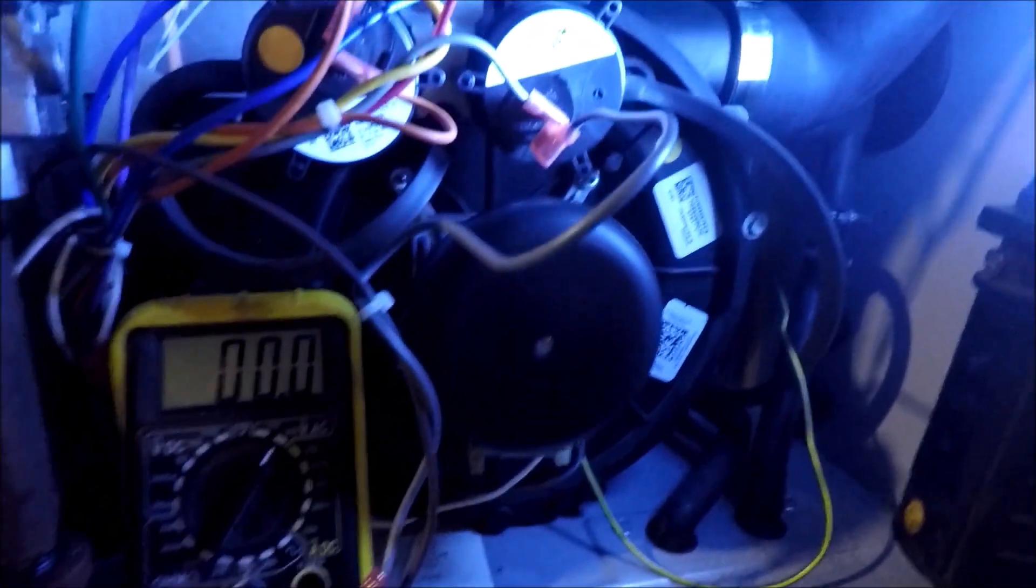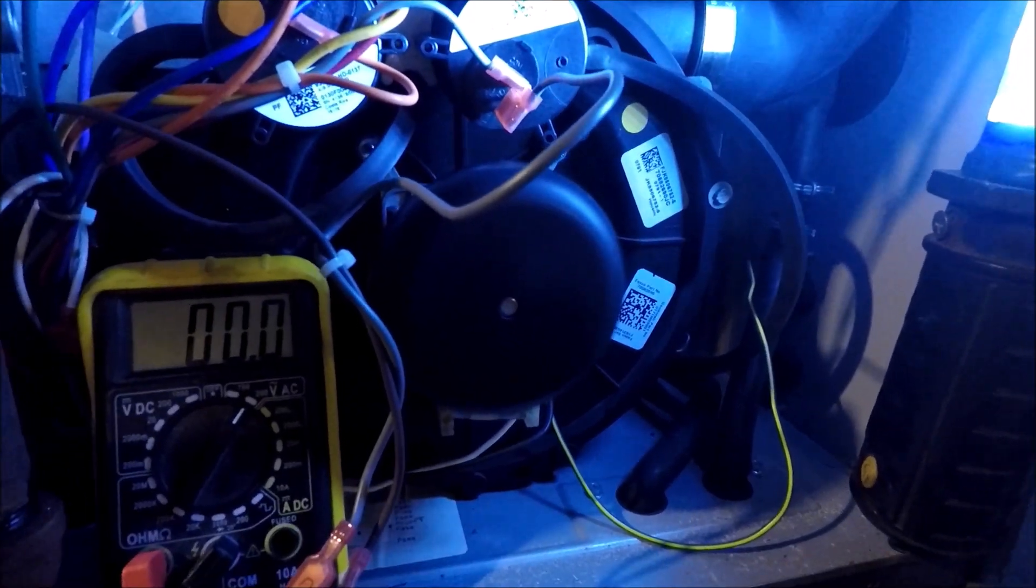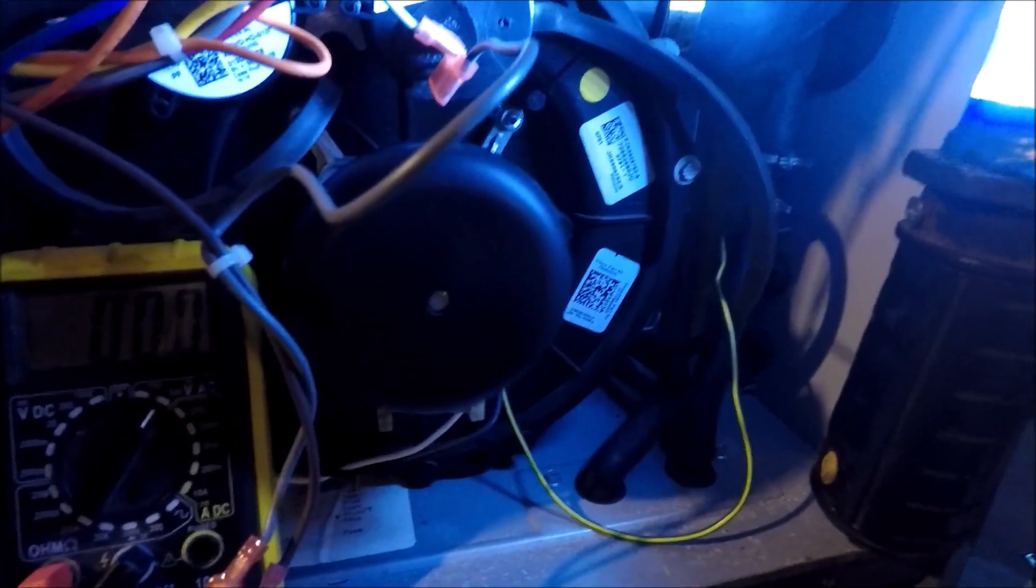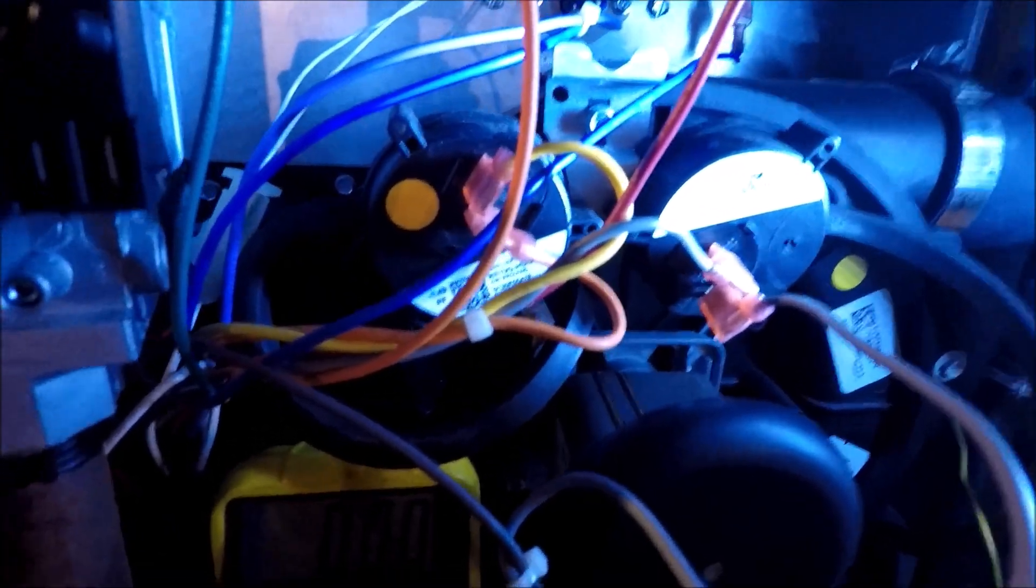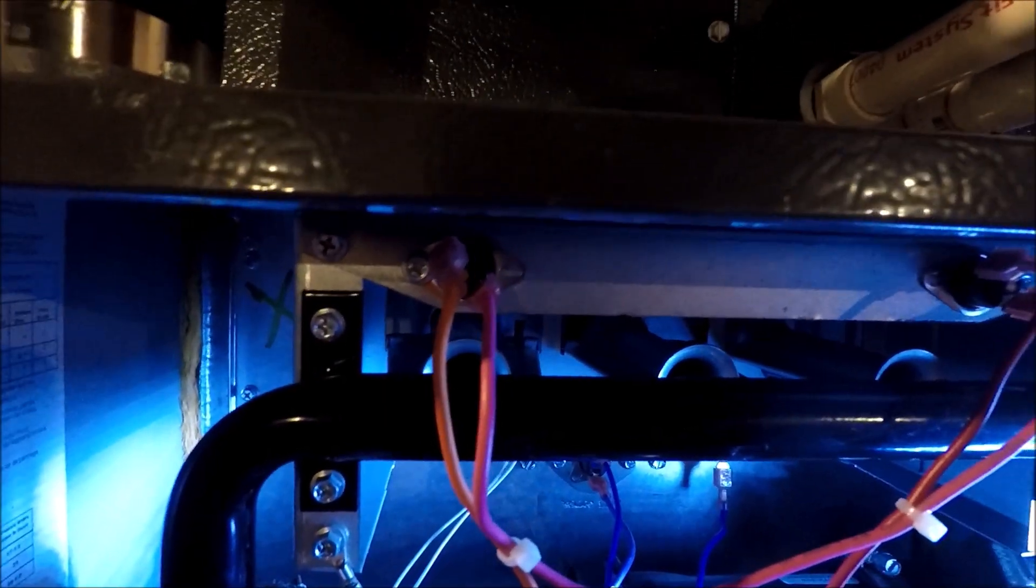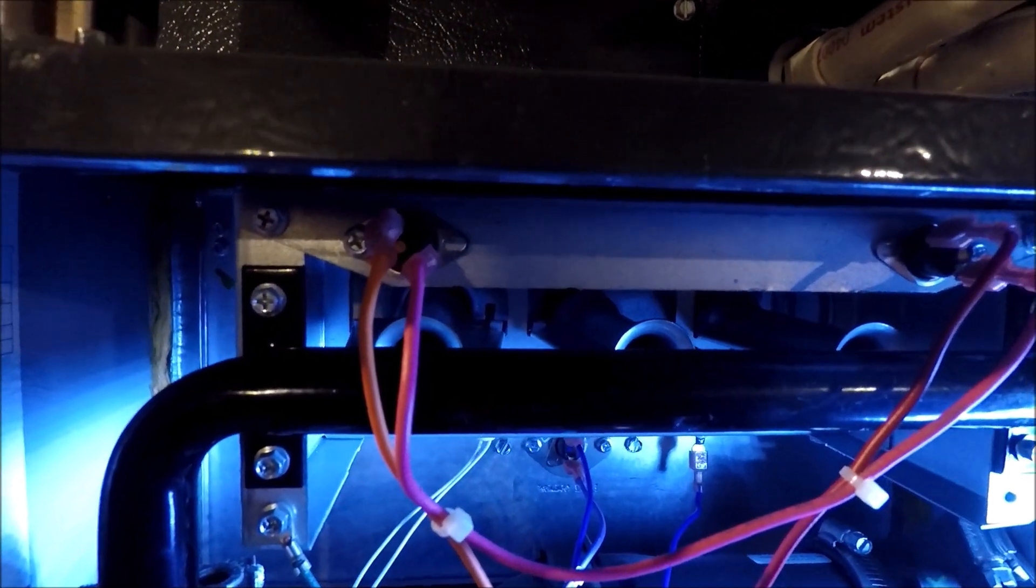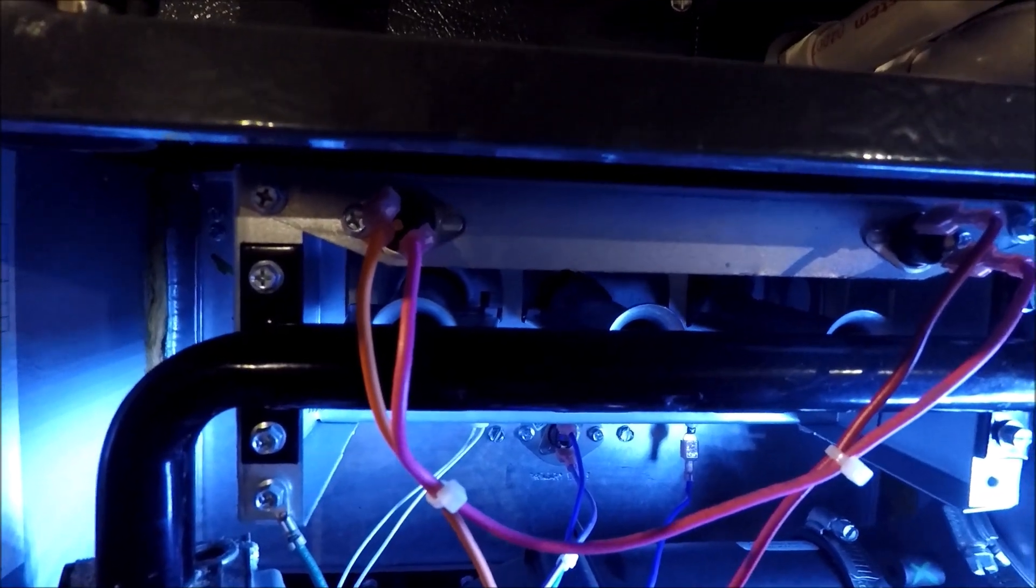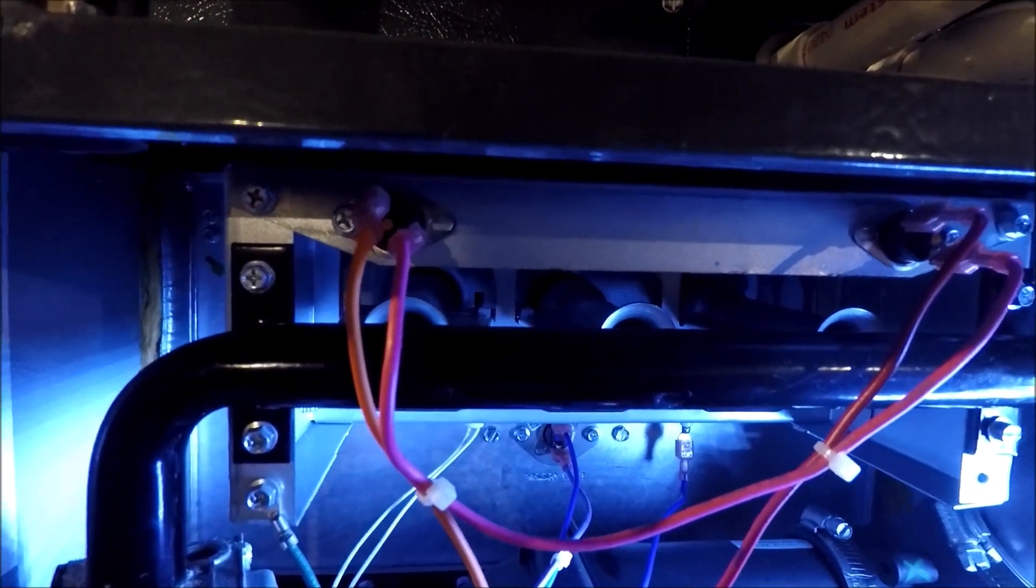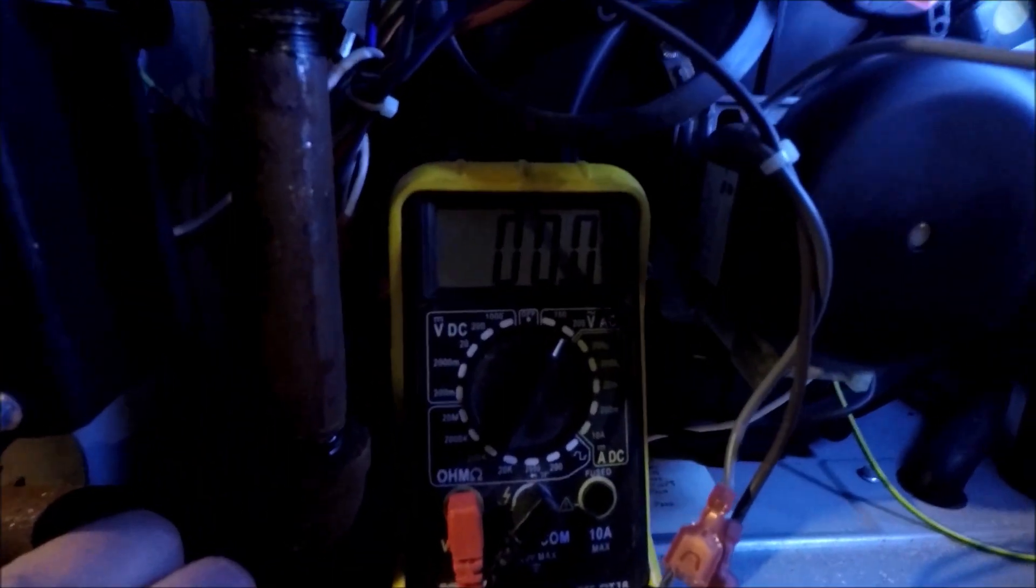So we have our gas heater come on. We check our pressure switches so we know they came on. Next we should have our igniter come on. We're waiting for the igniter, next to the gas valve to come on.